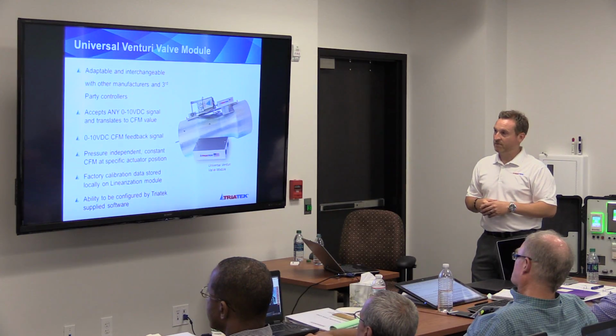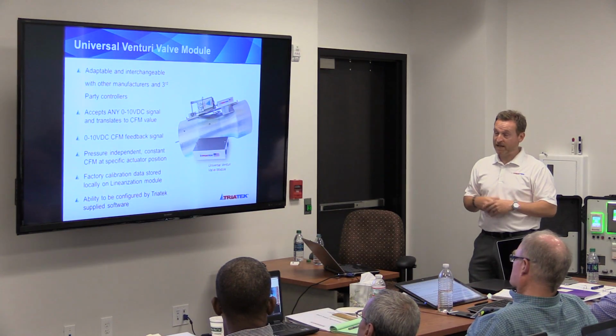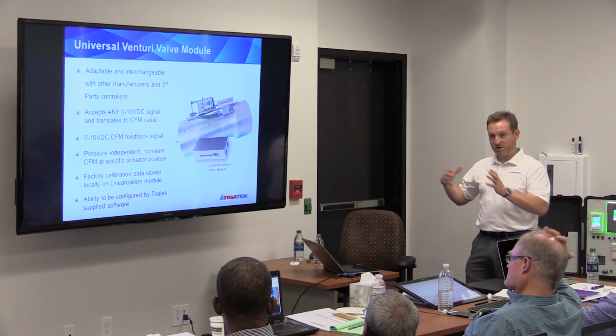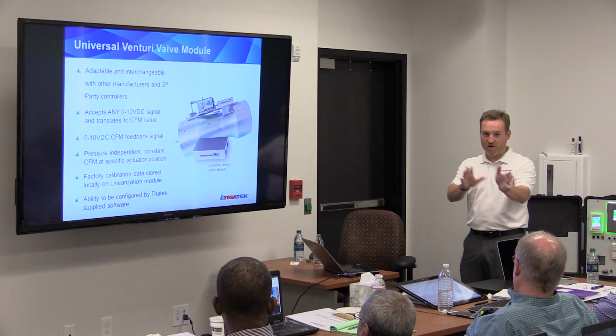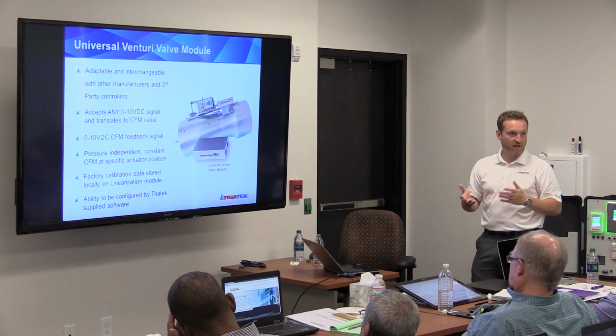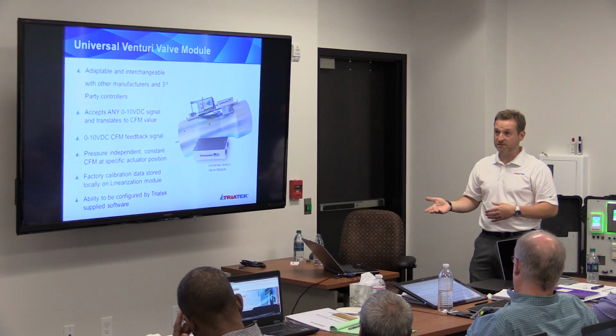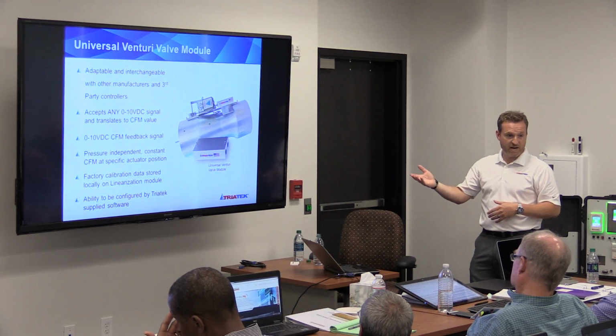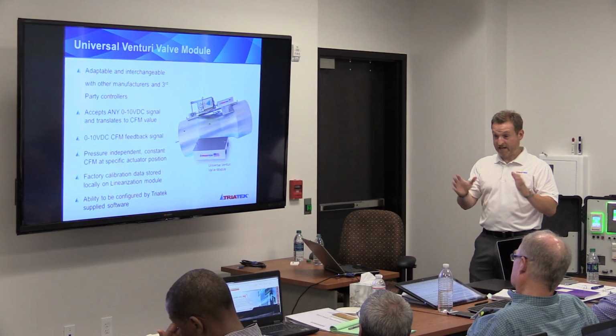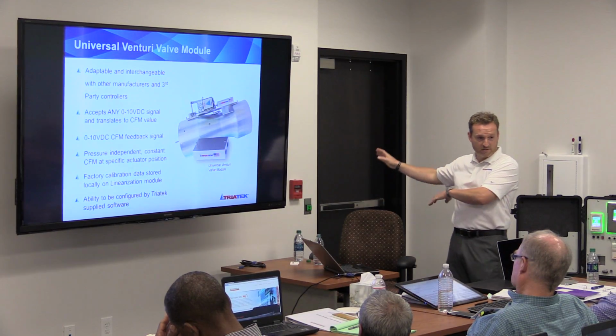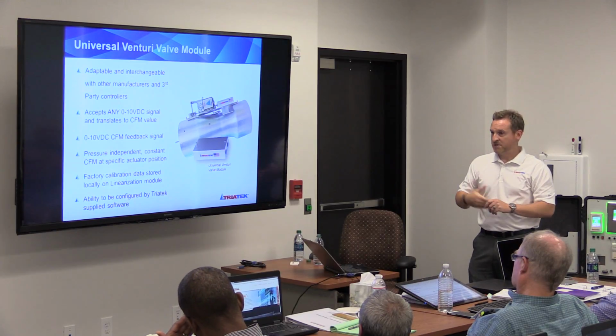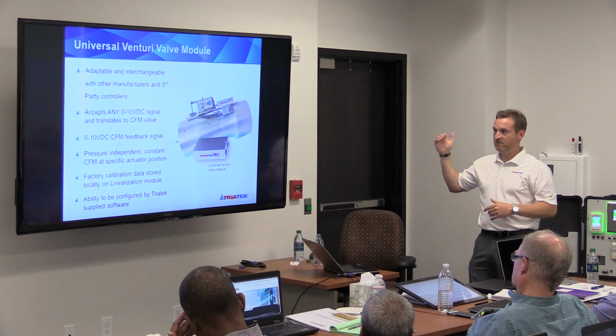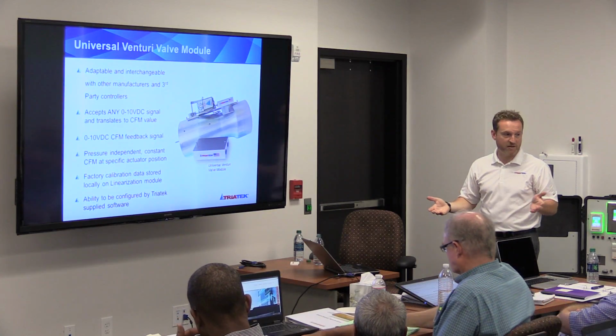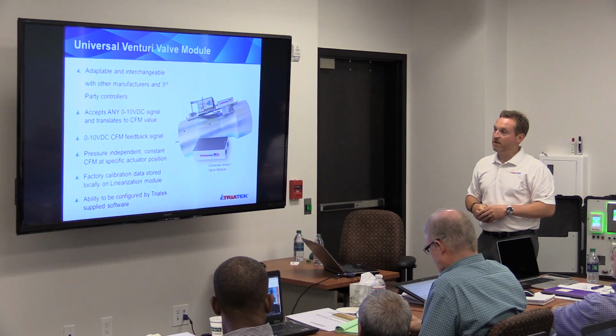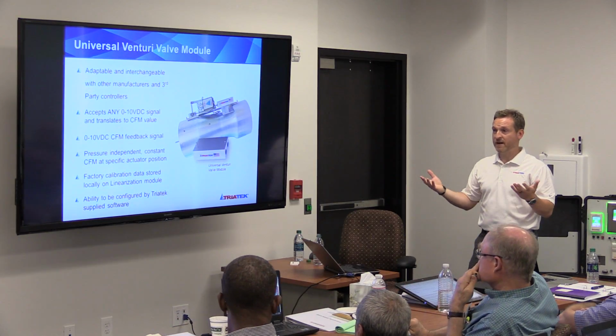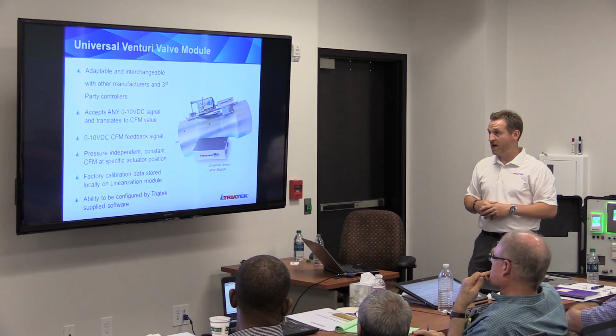Some of the other lab manufacturers, you get their control system, you get their valve, and you've got to use all their stuff. Well, we've broken that apart because we're seeing a lot of building management systems, particularly at colleges, where they want to use their own BMS to control these valves. One, it allows them to control their own destiny, not rely on someone else as a manufacturer. But we're seeing that most of the higher educational institutions have people and staff that manage their BMS and their controls. So the need was there, and we're getting a lot of positive response with this.